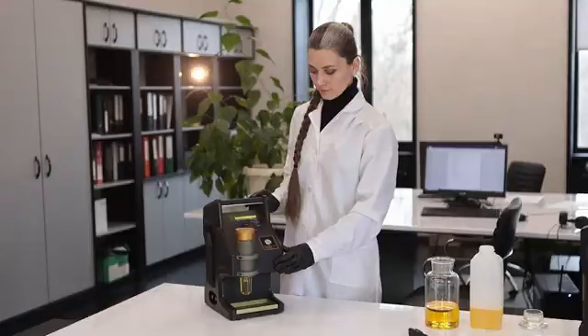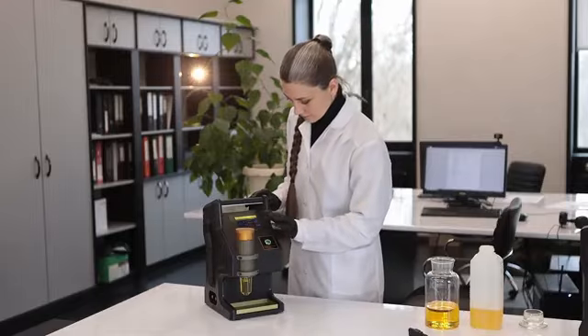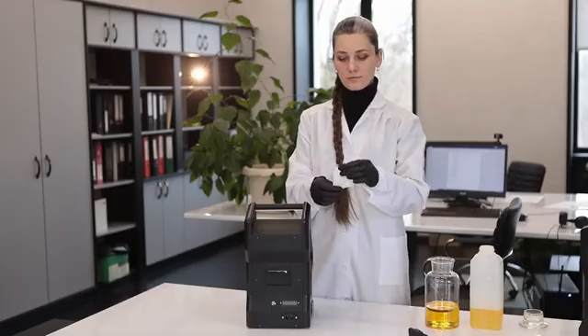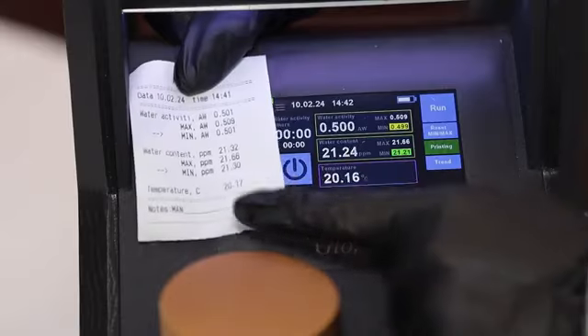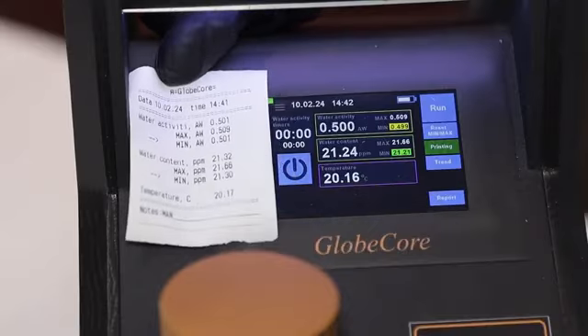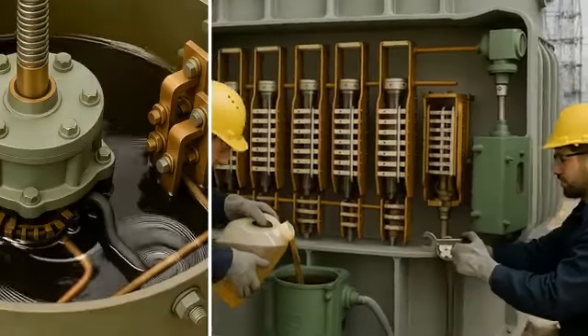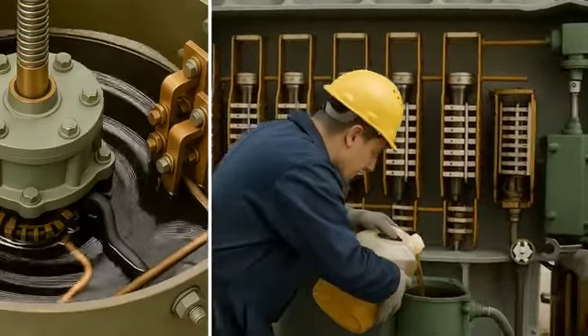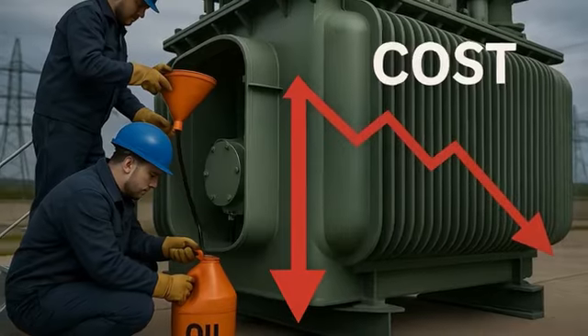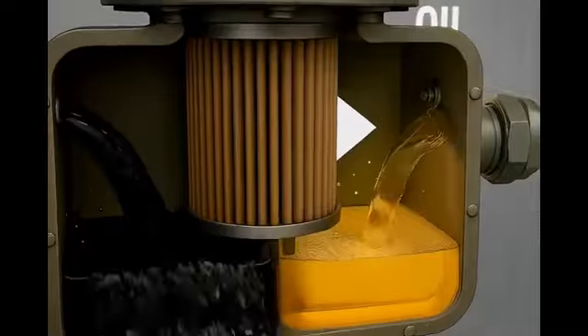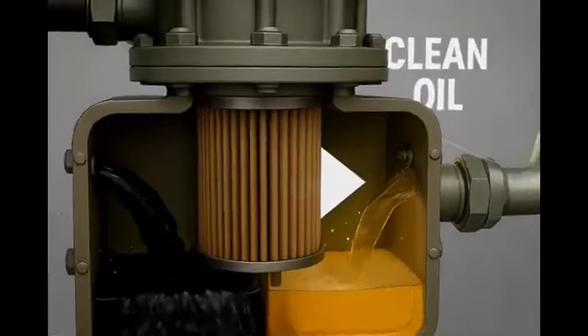If the test results show that at least one of the parameters does not meet the standards, moisture content or breakdown voltage, the tap changer tank oil should be changed. However, frequent change is not cost-effective. Thus, it is advisable to process the oil for moisture removal and to increase the breakdown voltage for reuse.